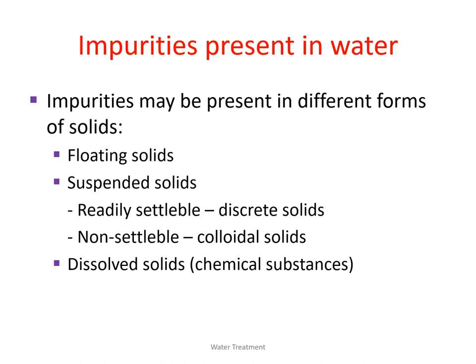These are the impurities. To convert water into clean water we must remove all suspended impurities. Suspended impurities contain floatable solids and other suspended solids. Among suspended solids we have readily settleable solids — also called discrete solids — and non-settleable solids called colloidal solids, which are charged solids. Colloidal solids are always negatively charged and cannot settle down in the sedimentation tank; they can remain suspended for months or even years. Therefore we need to take special care for this kind of colloidal solid.